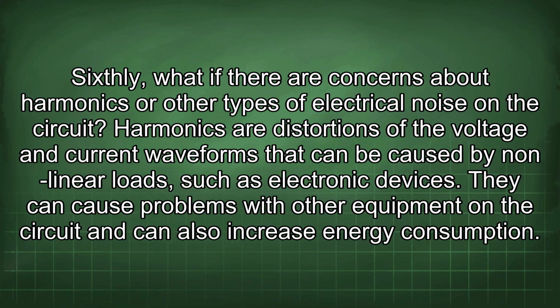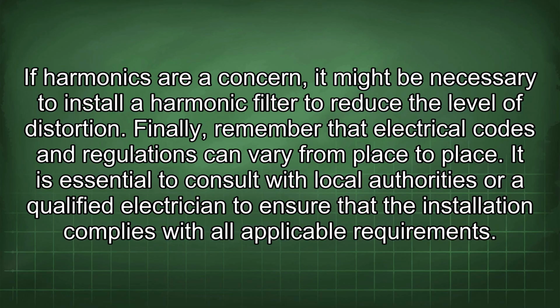Sixthly, what if there are concerns about harmonics or other types of electrical noise on the circuit? Harmonics are distortions of the voltage and current waveforms that can be caused by nonlinear loads, such as electronic devices. They can cause problems with other equipment in the circuit and can also increase energy consumption. If harmonics are a concern, it might be necessary to install a harmonic filter to reduce the level of distortion.